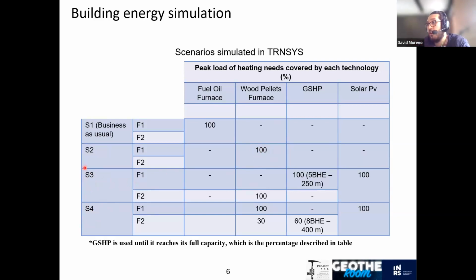In scenario 3, the heating needs of the first floor are covered by the geothermal source heat pump. In this configuration, I have 5 borehole heat exchangers of 50 meters each, to have a total of 250 meters of borehole heat exchanger length. The electricity needed to run the geothermal heat pump is covered 100% by the solar PV system. And the second floor in scenario 3 is covered by the wood pellet furnace.